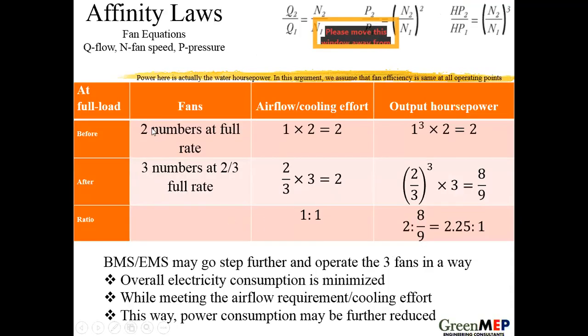This is what happens. Now, before, 2 fans, full rate. Let's say full means 100% or 1. You can say full means rated. Let's call it 1. 1 into 2, because there are 2 cooling towers, right? This is the cooling effort. Cooling effort is 1 into 2, 2, right? The flow, the cooling effort. The output horsepower, 1 to the power 3, because the speed is 1 or 100%. There are 2 of them, 2.